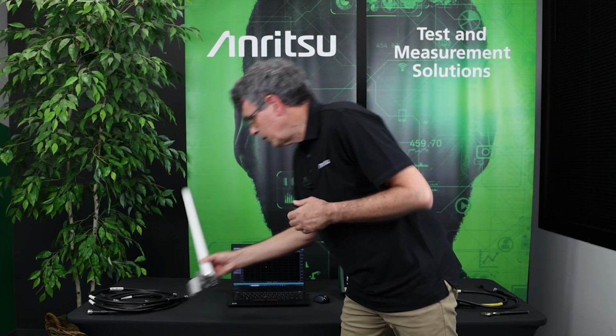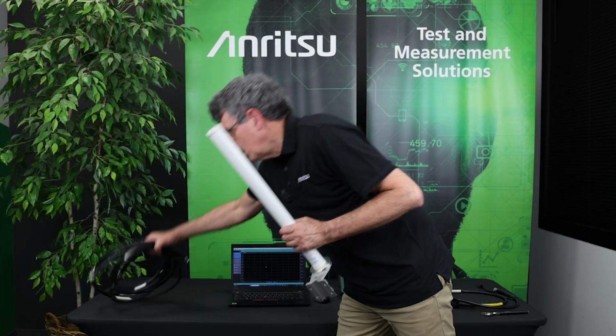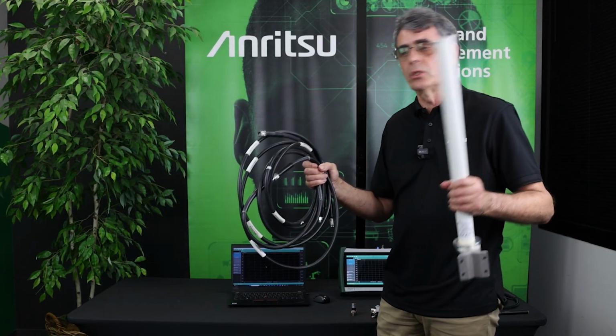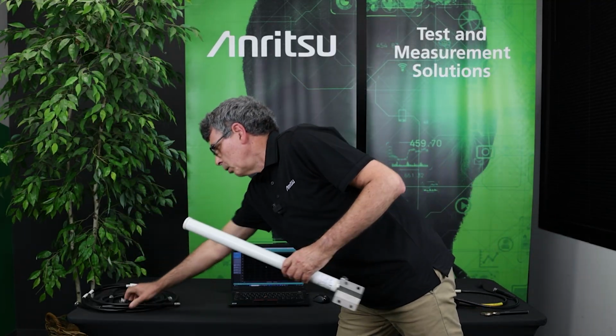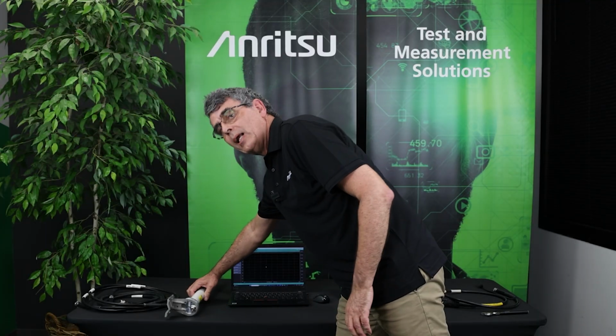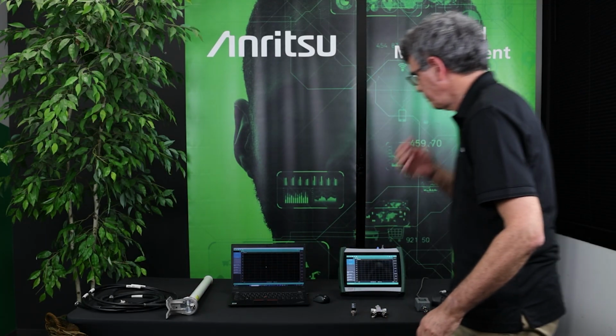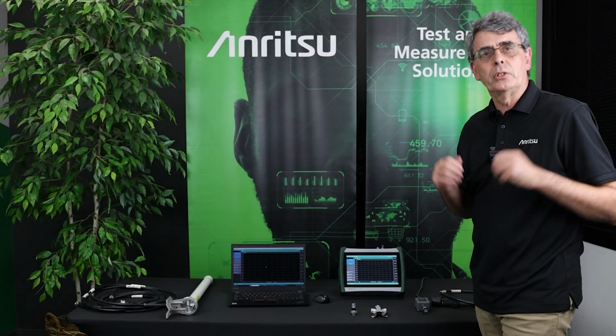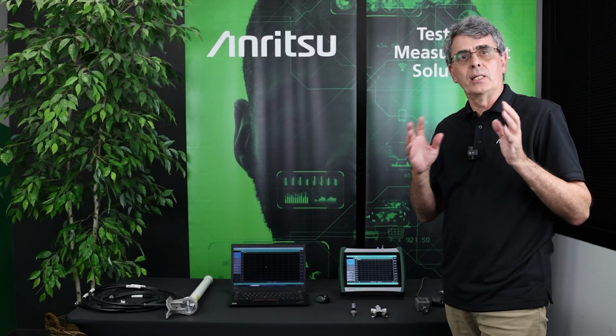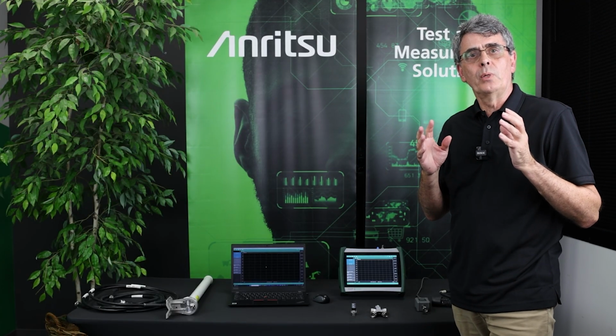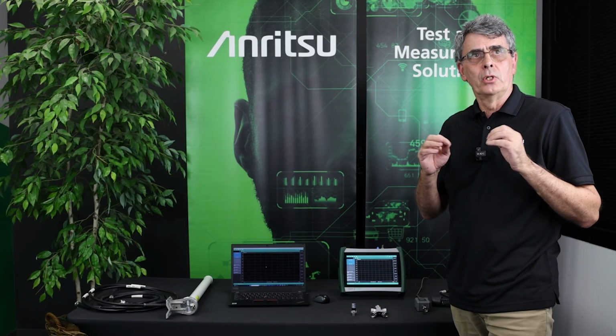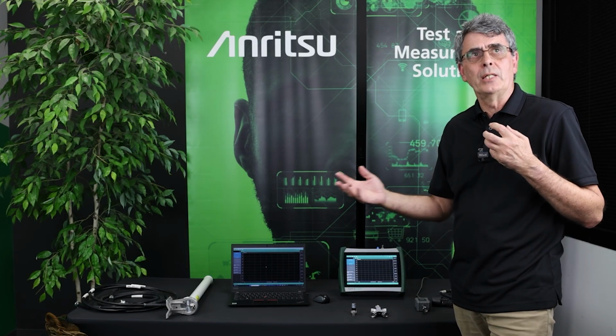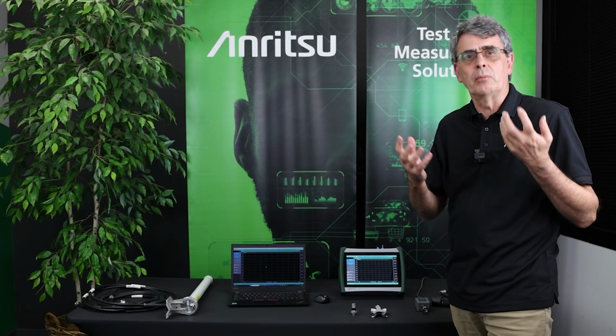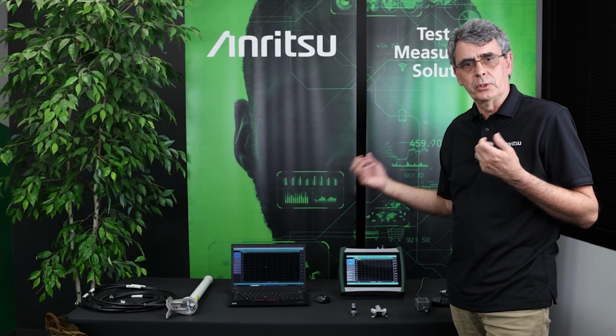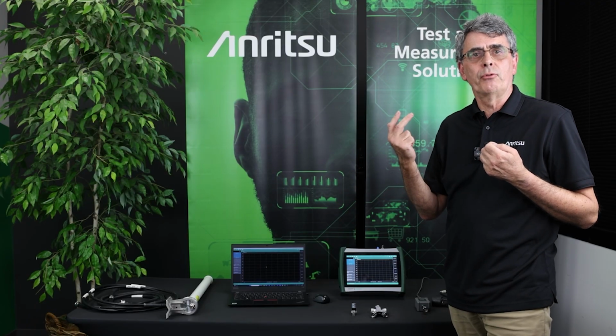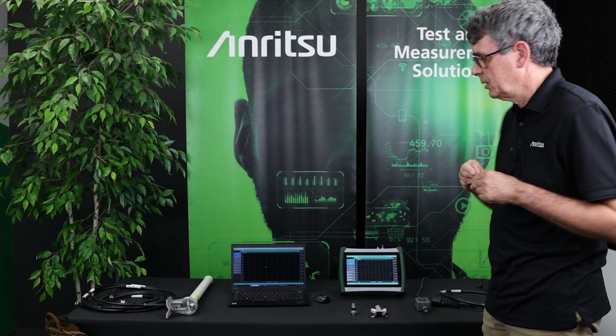So when we're installing and maintaining these sort of RF cables and antennas that are typically used on modern communication systems, either LMR or cellular, in order to measure the return loss on those antenna feeds, the first thing we always need to do is calibrate the instrument. We need to correct for source match errors, for directivity errors, for system errors at the test port. And with the SiteMaster we have three options as to how we can do that.